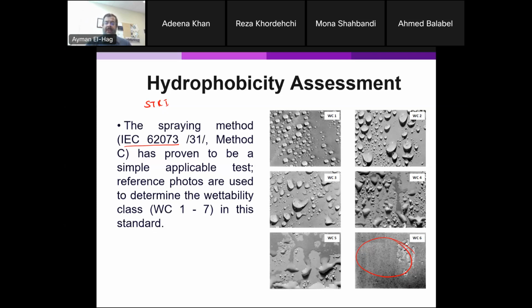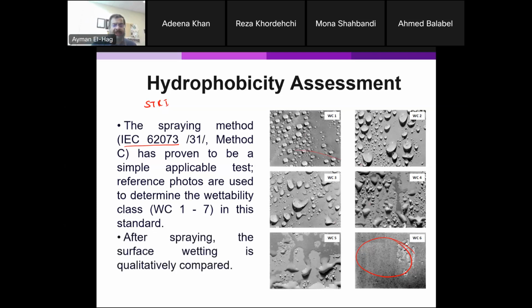And then, based on the guide, these pictures coming from the guide, you look at the pictures and you try to find which class the image you have belongs to. So class 1 and 2, you can see they are excellent. 3 and 4 are moderate, but 5, 6, and of course 7, when it is completely wet, these are bad, bad insulators.